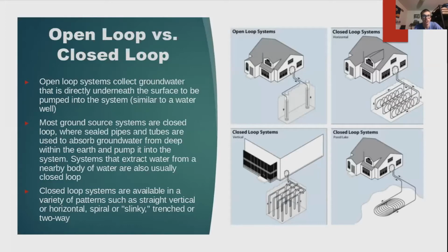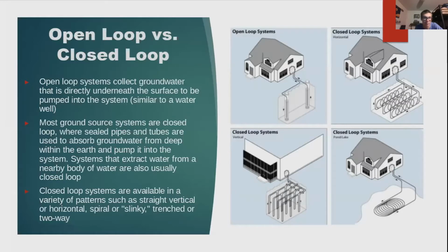Open loop versus closed loop. So open loop systems, as I just said, collect groundwater that is directly underneath. If the water table is super high, then you can just collect the water directly underneath without digging super deep. So think of a well. Most systems, though, are closed loop, where pipes and tubes are used to collect the water from deep underground, like up to 400 feet, and it's pumped to the system. And this includes systems that are collected from a lake or pond nearby. Those are usually also closed loop, despite it being a body of water nearby.